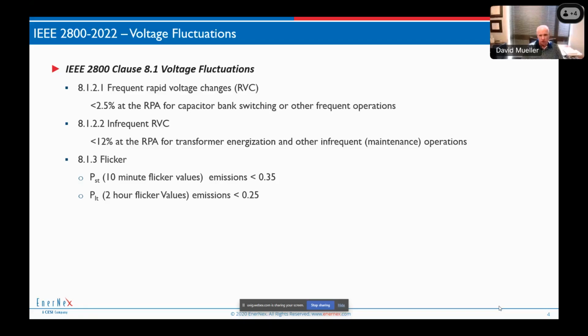So for frequent, what is frequent? Frequent is anything that's not infrequent. And forgive me, infrequent would be transformer energization and other maintenance operations. So things that happen, I don't know, once a week, once a month, something like that. Whereas frequent would be daily types of things. If I tried to put a time on it, the standard doesn't really define it any more than what I've shown here. So in frequent, we want to have less than 2.5% voltage variation in RPA due to the plant operations. And capacitor banks is one of the things that can obviously step the voltage.